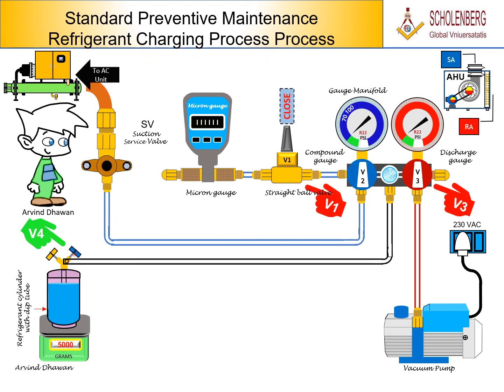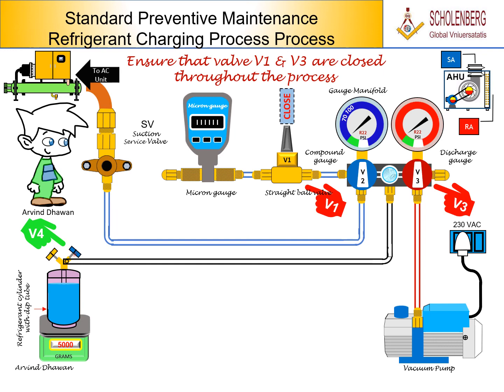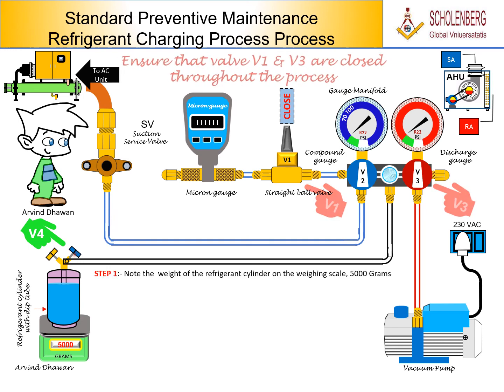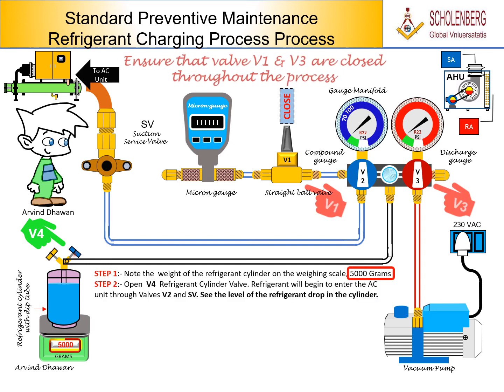Refrigerant charging process. Ensure that valves V1 and V3 are closed throughout the process. Step 1. Note the weight of the refrigerant cylinder on the weighing scale, 5,000 grams. Step 2. Open V4 refrigerant cylinder valve. Refrigerant will begin to enter the AC unit through valves V2 and SV. See the level of the refrigerant drop in the cylinder.